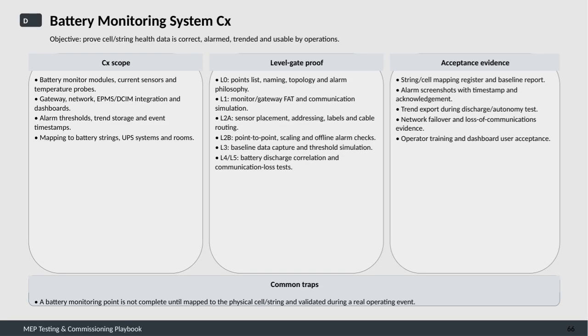The main objective here is to ensure that the health data from each cell or string is not only accurate, but also properly alarmed, trended over time, and usable by the operations team. This involves verifying several key components, including battery monitor modules, current sensors, and temperature probes. We also need to confirm that the gateway, network integration, and dashboards like EPMS or DCIM are functioning correctly. Alarm thresholds, trend data storage, and event timestamps must all be validated. Additionally, mapping these monitoring points to the corresponding battery strings, UPS systems, and physical rooms is crucial for operational clarity.